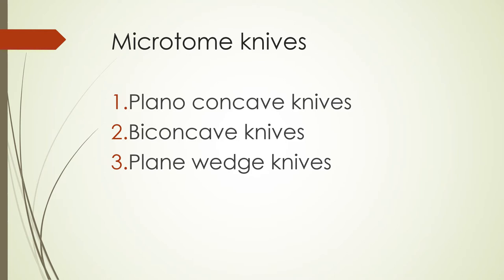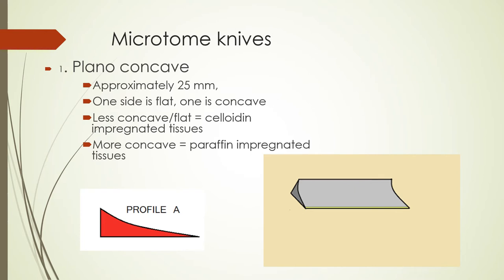For microtome knives, we have three types: the planoconcave, the biconcave, and the plane wedge knives. These are not disposable — they are regularly maintained by honing and stropping. Starting with the planoconcave, it is approximately 25 millimeters long. One side is flat and one side is concave in shape. The less concave or flat side is used for celloidin-impregnated tissues, and the more concave side is used for paraffin-impregnated tissues.